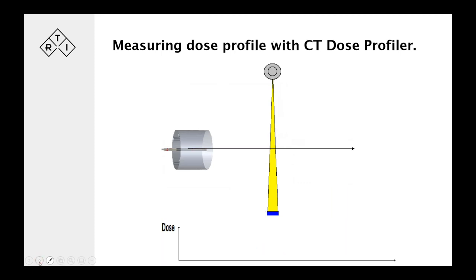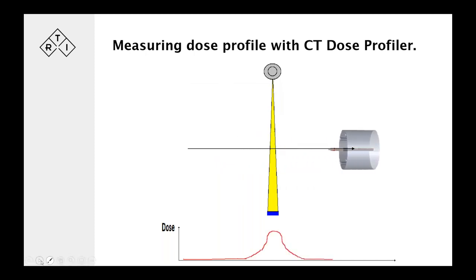So it would look something like this if we try to animate it. It pushes through and then it rises, and as it goes through, we have data about it. So we use the CT Dose Profiler in a way where we scan the dose. We sample the dose in the center of the CT Dose Profiler, which is in the center of the phantom, with a known sample frequency.